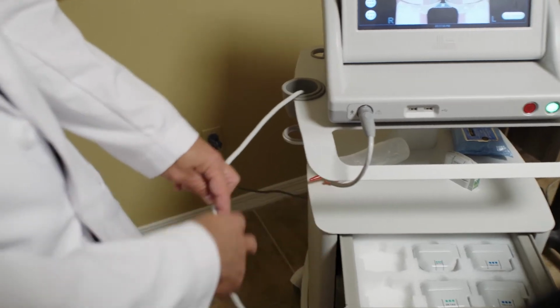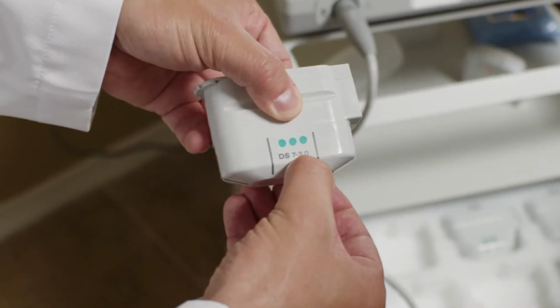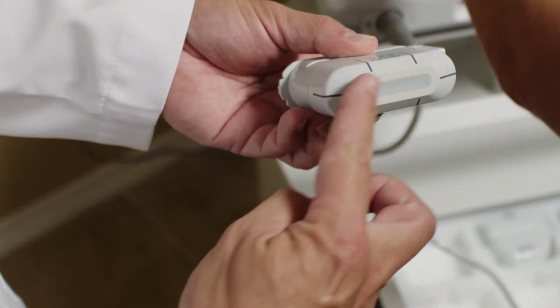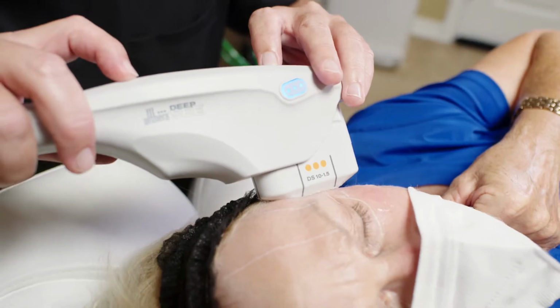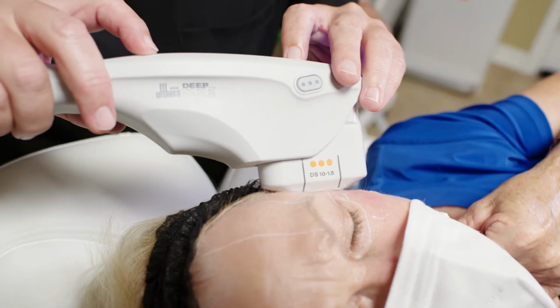The procedure involves using ultrasound energy at varying depths to tighten the skin and to create a lifting effect. So there are numerous heads that go on the device that have multiple ultrasound probes in them that will cross each other at a certain depth. And at the depth that those ultrasound waves cross, it creates a thermal coagulation point or a heat point, which will cause a little bit of tissue damage. And as that tissue heals, you're going to stimulate collagen and create lifting in that area.